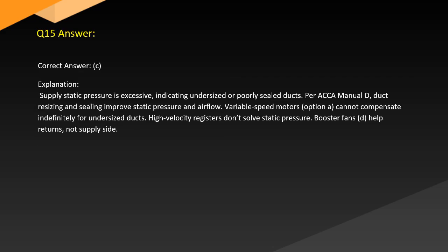Answer. Correct answer: C. Explanation. Supply static pressure is excessive, indicating undersized or poorly sealed ducts. Per ACCA Manual D, duct resizing and sealing improve static pressure and airflow. Variable speed motors, option A, cannot compensate indefinitely for undersized ducts. High-velocity registers don't solve static pressure. Booster fans, D, help returns, not supply side.